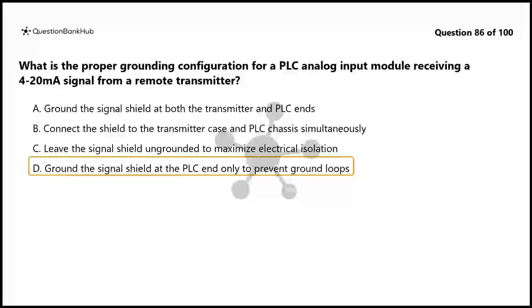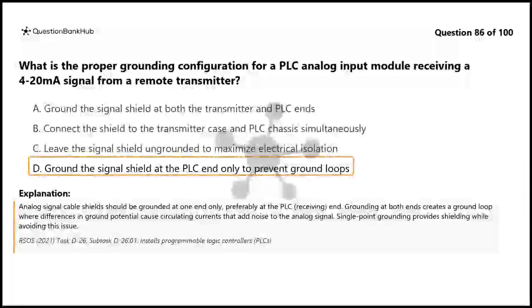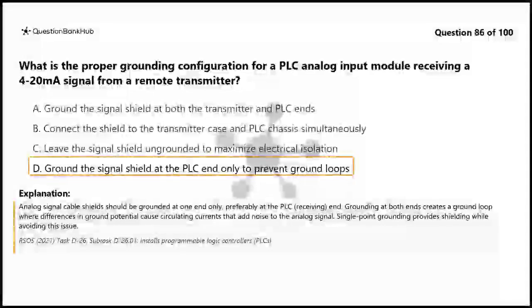The correct answer is D. Ground the signal shield at the PLC end only to prevent ground loops. Analog signal cable shields should be grounded at one end only, preferably at the PLC receiving end. Grounding at both ends creates a ground loop where differences in ground potential cause circulating currents that add noise to the analog signal. Single-point grounding provides shielding while avoiding this issue.